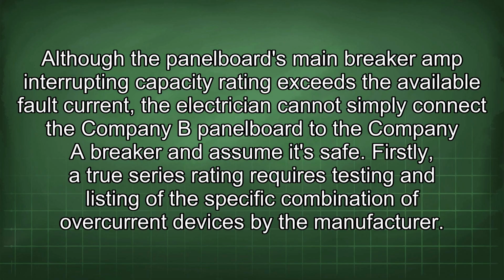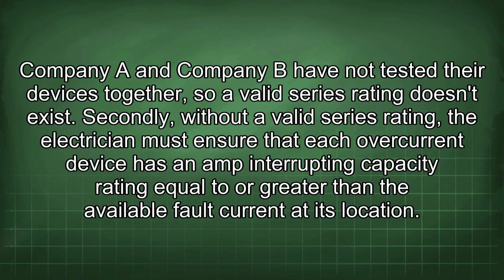Although the panelboard's main breaker amp interrupting capacity rating exceeds the available fault current, the electrician cannot simply connect the Company B panelboard to the Company A breaker and assume it's safe. Firstly, a true series rating requires testing and listing of the specific combination of overcurrent devices by the manufacturer. Company A and Company B have not tested their devices together, so a valid series rating doesn't exist. Secondly, without a valid series rating, the electrician must ensure that each overcurrent device has an amp interrupting capacity rating equal to or greater than the available fault current at its location.